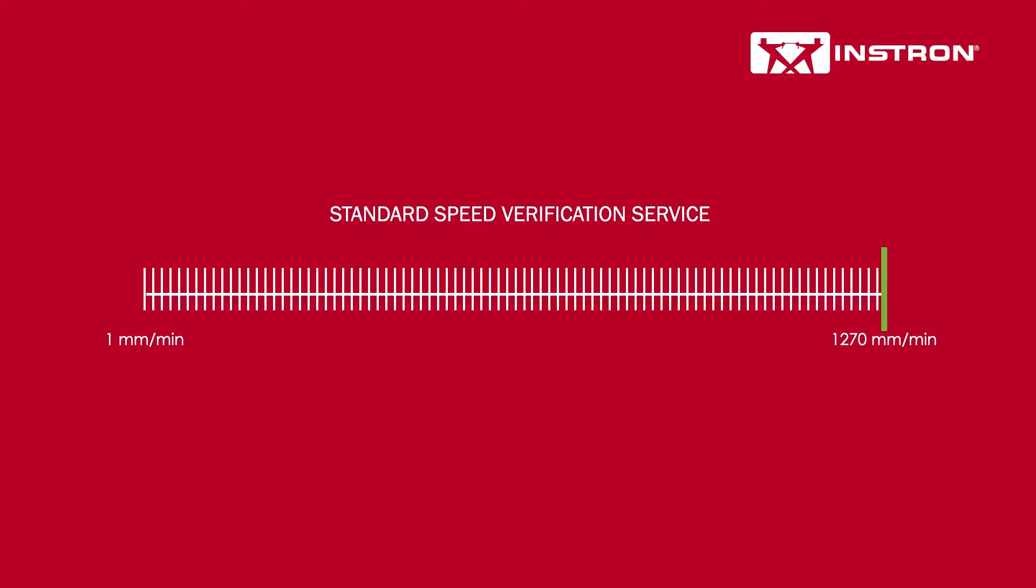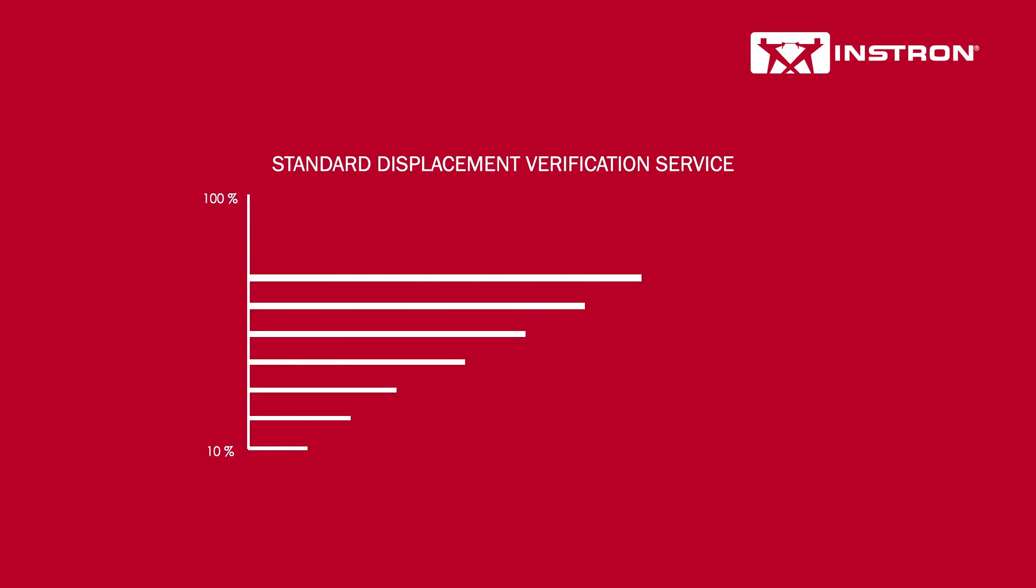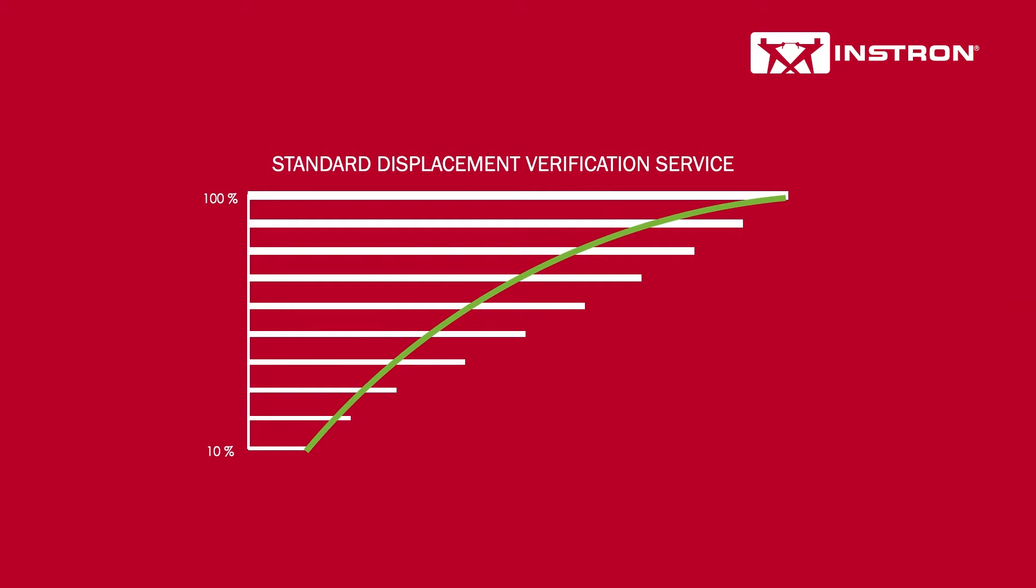Slower and faster speeds can also be calibrated if required. For standard displacement calibration we cover 10% to 100% of customer selected ranges.